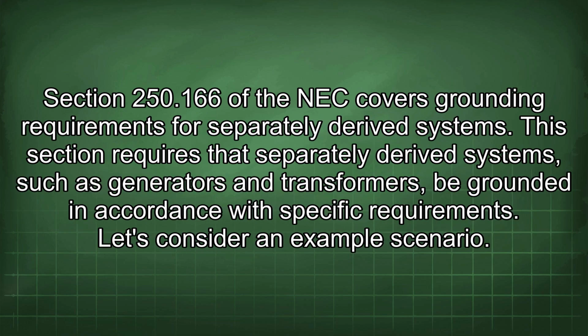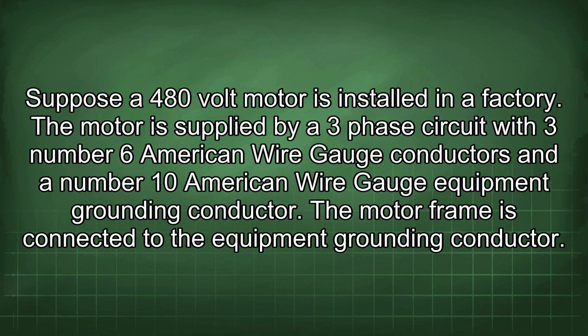Section 250.166 of the NEC covers grounding requirements for separately derived systems. This section requires that separately derived systems, such as generators and transformers, be grounded in accordance with specific requirements. Let's consider an example scenario. Suppose a 480-volt motor is installed in a factory. The motor is supplied by a three-phase circuit with three number 6 American wire gauge conductors and a number 10 American wire gauge equipment grounding conductor. The motor frame is connected to the equipment grounding conductor.